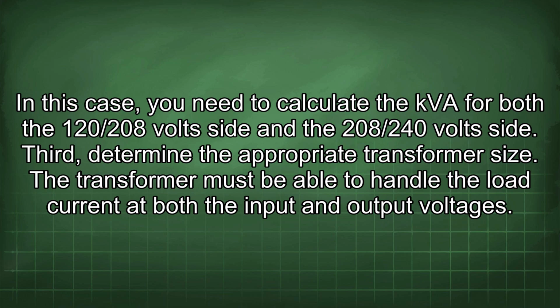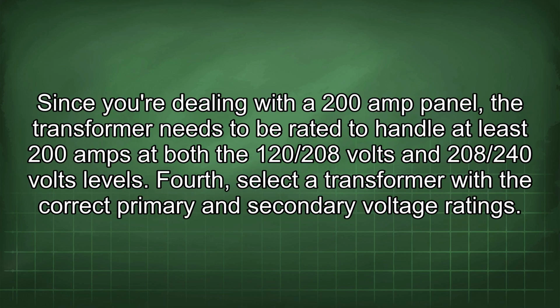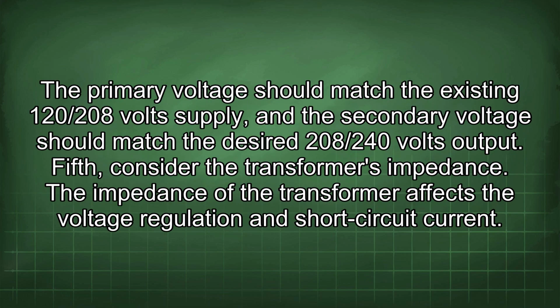Third, determine the appropriate transformer size. The transformer must be able to handle the load current at both the input and output voltages. Since you're dealing with a 200 amp panel, the transformer needs to be rated to handle at least 200 amps at both the 120/208 volts and 208/240 volts levels. Fourth, select a transformer with the correct primary and secondary voltage ratings. The primary voltage should match the existing 120/208 volts supply, and the secondary voltage should match the desired 208/240 volts output.